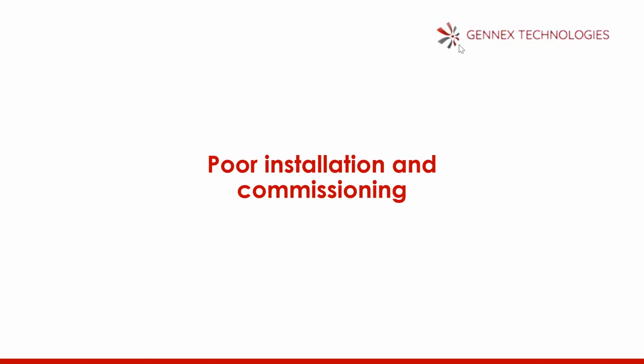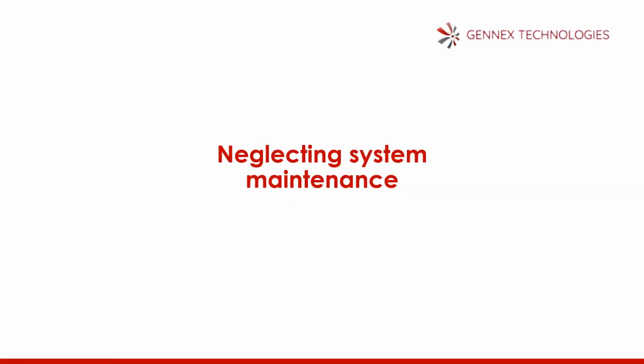The next one is neglecting system maintenance. We have three categories of batteries: the lead acid, which is the flooded, the AGM and the gel, and we have the lithium. Each one of them has certain maintenance that needs to be put in place. That's in terms of batteries. Now, what is the maintenance? For the flooded batteries, there's need to check the electrolyte level, and most manufacturers advise you top up with distilled water. So as the level goes down, you check from time to time.